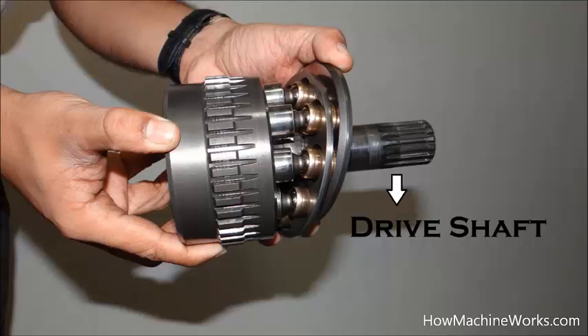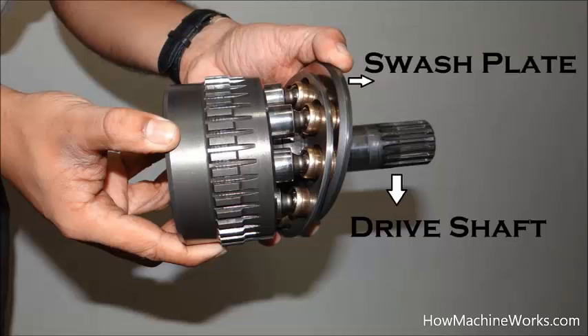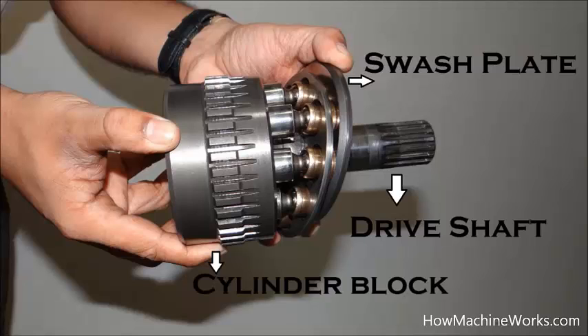That's the drive shaft, which is a part of the cylinder itself. The drive shaft gives drive towards the cylinder, and that's the swash plate, which I told the pistons are resting and sliding over. The swash plate angle changes, the flow varies. That's our cylinder block in which we have the pistons arranged, and as the cylinder block rotates, the pistons slide over and actually reciprocate. That's the pistons over there.